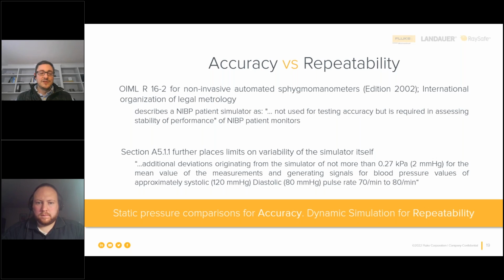So it is an inexact science, but it is possible to measure the repeatability of these simulations. Without delving too far into that, the next slide will compare accuracy and repeatability. I won't read all of this, but the International Organization of Legal Metrology's recommendation on non-invasive automated sphygmomanometers describes an NIBP patient simulator as, quote, not used for testing accuracy, but required in assessing the stability of performance of NIBP patient monitors.